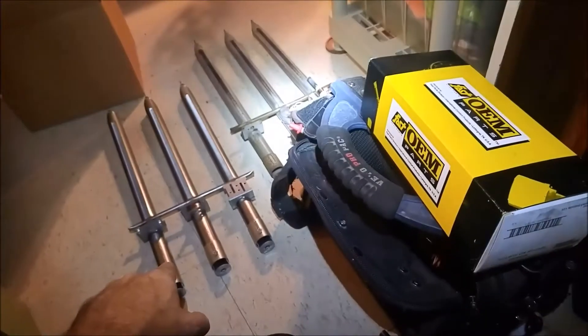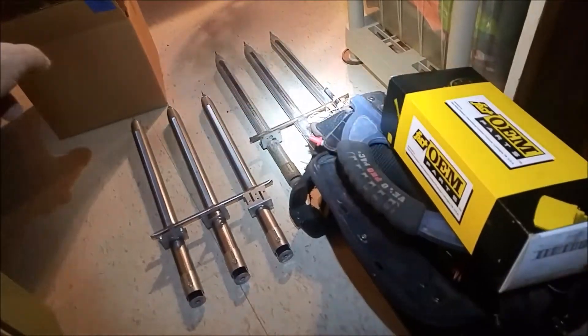I was out here on Sunday, no heat, bad inducer motor. Got a replaced inducer motor and we had burners that were rotted out. You can see them right there - just rotted out. I got new burners here. Comes with an igniter kit. And we got the new inducer motor there. So we got to put the new igniter kit on here, flame sensor, inducer motor.